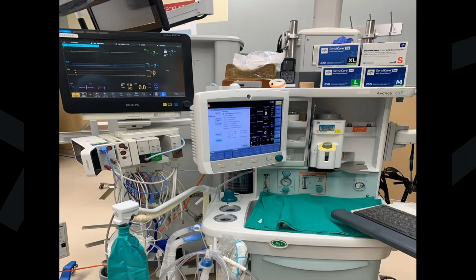So here's a basic setup on your anesthesia cart. Right here's your attached aftermarket monitor. In this case it's Philips, and it's on a GE machine. So this thing can operate independently of the rest of the cart. Now this particular screen is in relation to the machine itself. So when you're doing your diagnostics, your maintenance, your self-tests, as well as setting your rate on your ventilator, will all be done from this screen that's actually part of the machine.